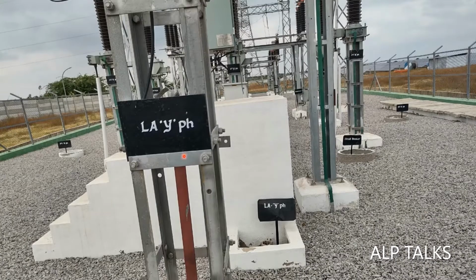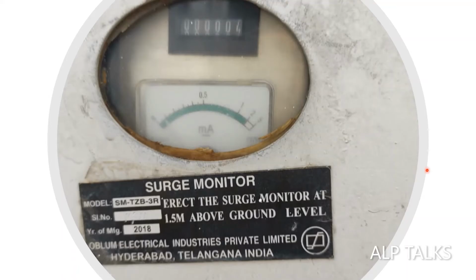Here we can see the LA, lightning arrestor. Generally they place the lightning arrestor and solidly ground it directly at the same place. They will use copper or GI. I think they will use copper for the LA, and for the remaining they can use GI. This is the surge monitor, located at each surge arrester. Here we have four surge monitors. They record milli current and current also. We can see whatever leakage current is there.